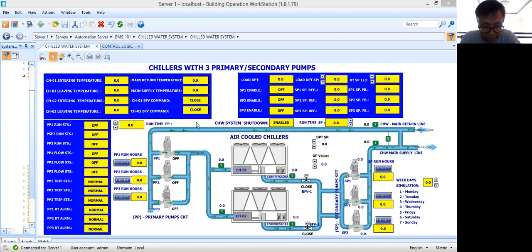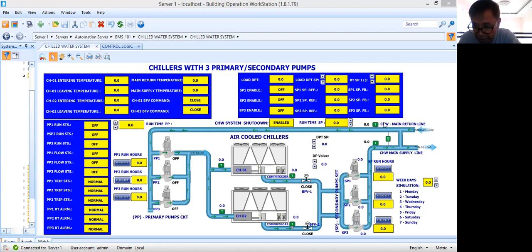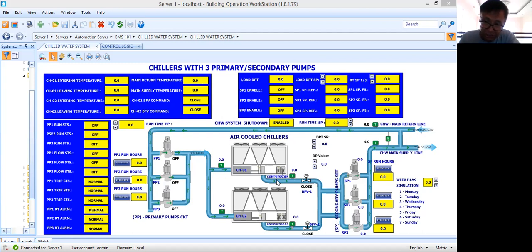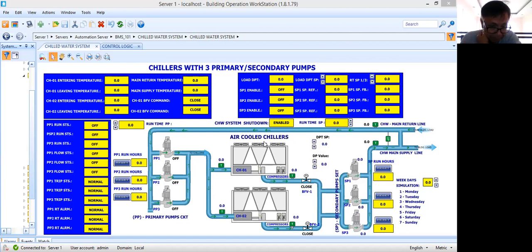Likewise for chiller two, I will have entering temperature and leaving temperature here. Then I will be monitoring the main return line temperature, because based on this temperature I will try to add and shed the chillers — there will be a time that only one chiller is needed to handle the building load, and there will be a time that we need two chillers, especially during summertime. Now for the primary pumps, we have monitoring points: run, flow, trip, and also the runtime alarm.